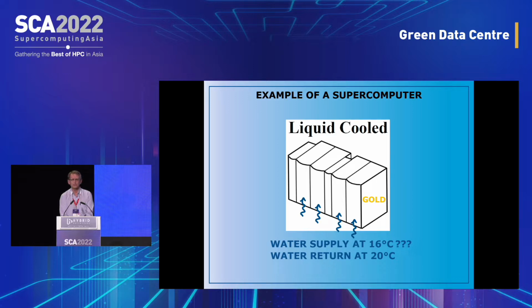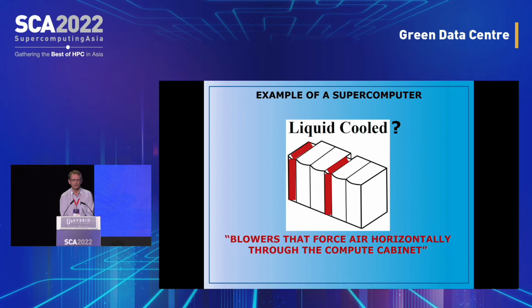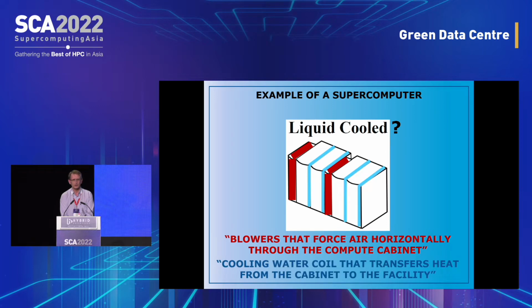Why does it need to be so cold? Looking further at the manual we see words like cabinet air temperature set point, 21 degrees. I'm starting to get suspicious - why are we talking about air temperature? This is a liquid-cooled server. Looking further through the documentation we find there are blowers that force air horizontally through the compute cabinet. Sounds impressive. And we've got a cooling water coil that transfers heat from the cabinet to the facility.